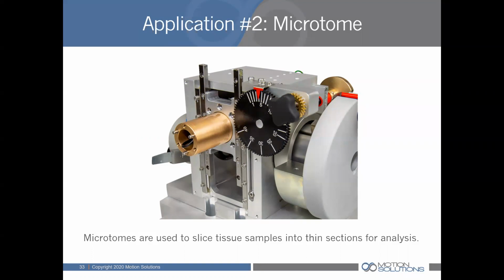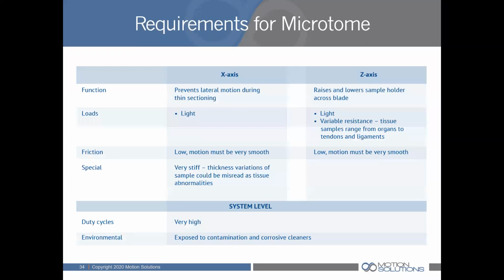Users of this equipment call it Venetian blinds. That is lines, vertical or horizontal, across the sample, going through the sample, many, many lines that kind of look like a Venetian blind. And when that happens, the sample is just unusable. You can't look at it. You can't look at the cells under the microscope. So it's very important here to have maximum rigidity.